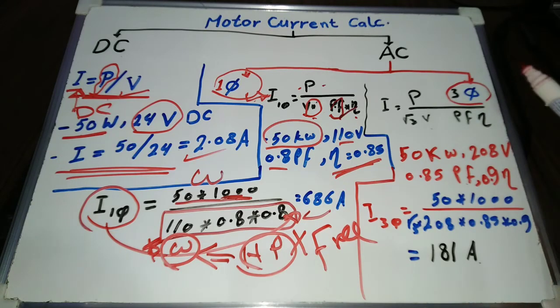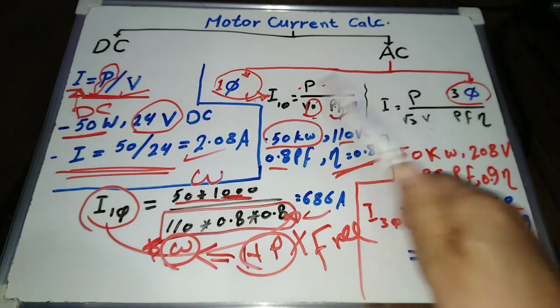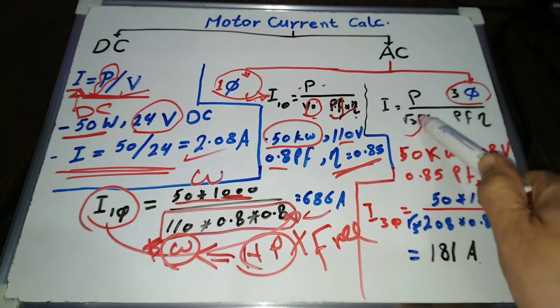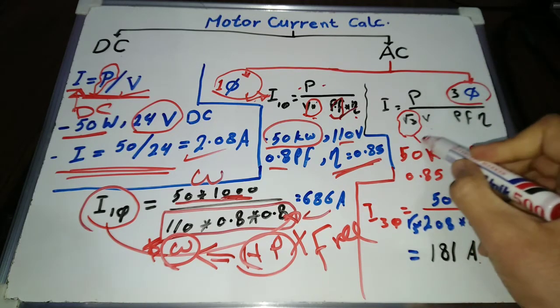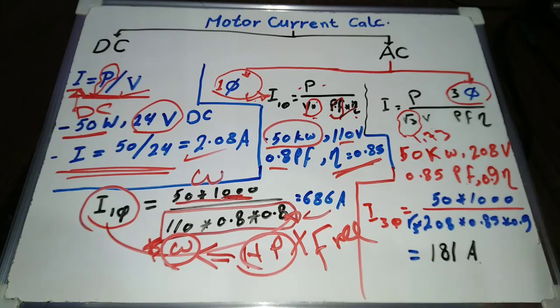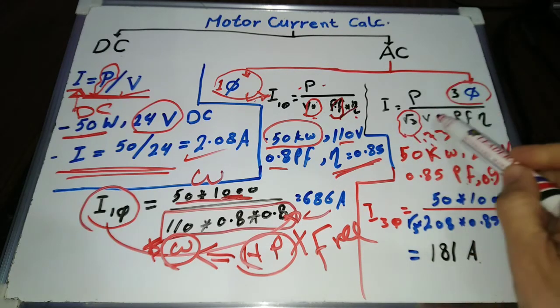Three phase motor current equation is the same as single phase motor equation, except one thing: 1.73 in the equation. Three phase current equals power divided by 1.73 times voltage times efficiency times power factor.